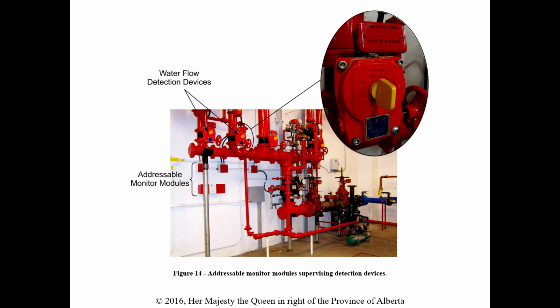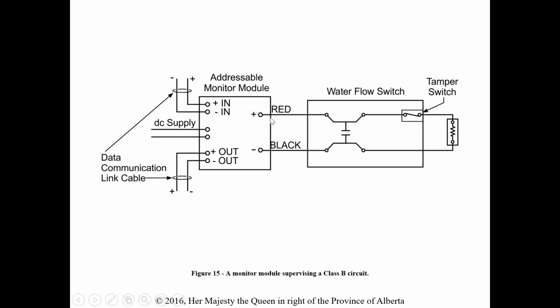So for a valve, for a fire pump, or for a sprinkler system, it needs to be open. We can use an addressable monitor module to make sure that that does stay open, and if it closes, send a signal back to the panel. So we can use those. So here's what it would be like. We would have our DCL cables coming in here, again constantly reading, is this thing good? Yep, yep, yep. And then we have our field section where we come from the addressable monitor module out to the flow switch. And then we still have an end-of-line resistor here too, because this module is going to read this current coming back through here.